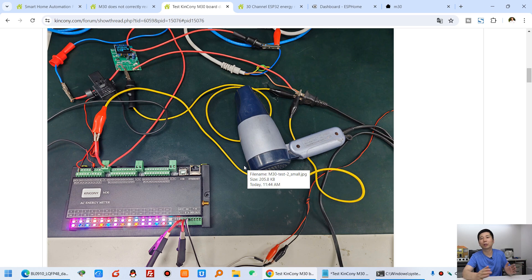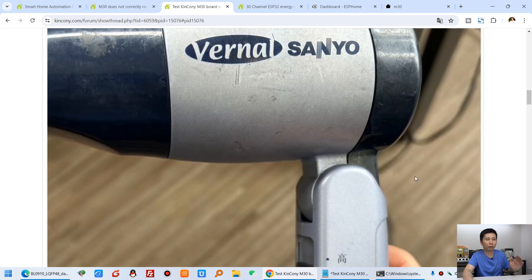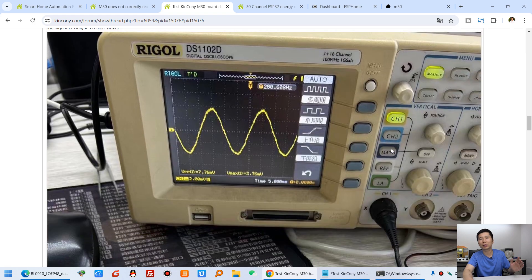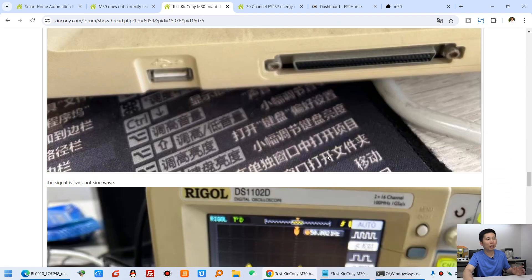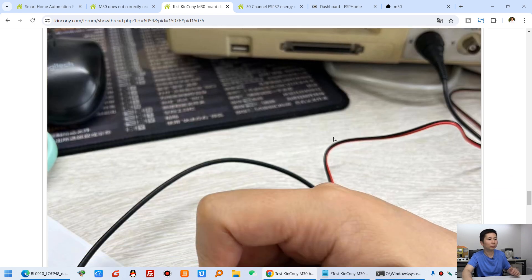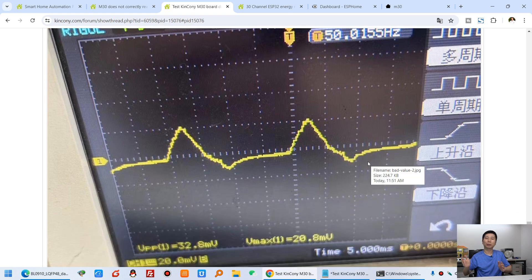We think the M30 itself has no problem. The main problem is the CT sensor. We used a hair dryer to test — it has two positions: low and high, just different power. At max power, a high load, the signal is almost a sine wave, so the signal is well. But when we tested the CT sensor output with a 10-ohm resistance, the signal is very good at high load. However, when we change to middle load power, the signal is bad, and that makes the data incorrect.